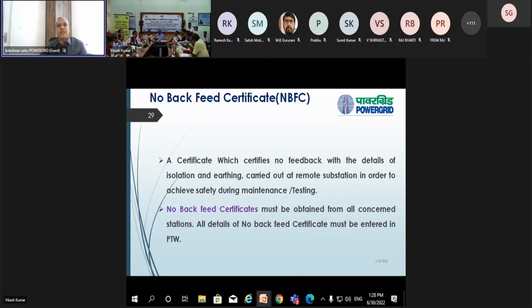For the transmission line, the most important is the no back-feed certificate. We certify no back-feed, with the details of the isolation and earthing carried out at the remote station, in order to achieve safety during maintenance and testing. The no back-feed certificate must be obtained from all concerned stations. All details of the NBC must be entered in the PTW. This is very important for any transmission line maintenance or line equipment maintenance.